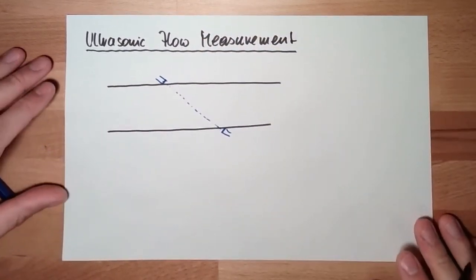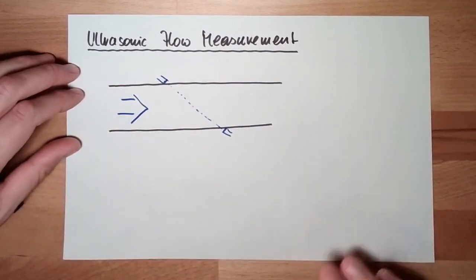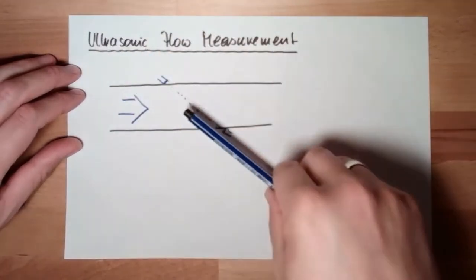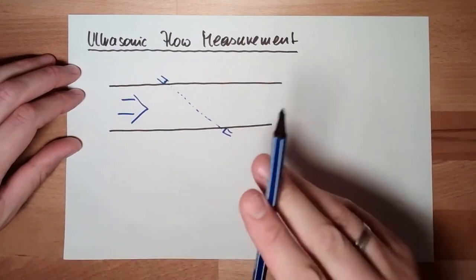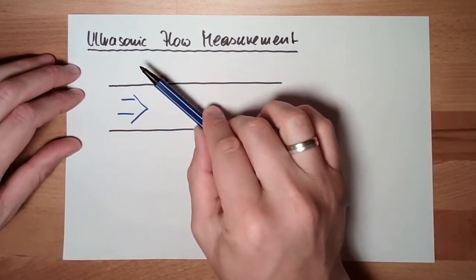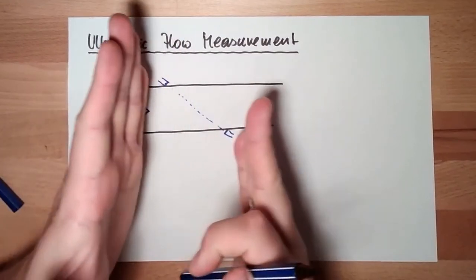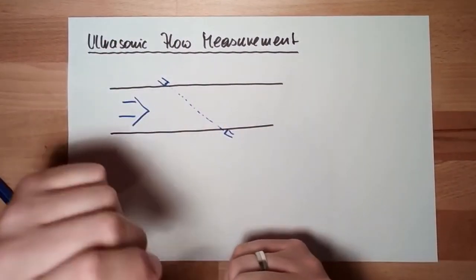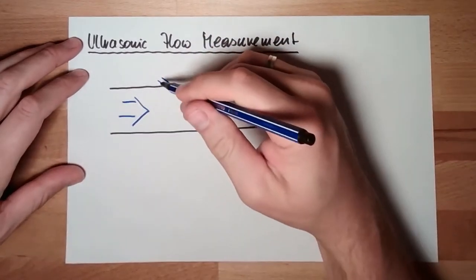It works that way that if we have flow here, the sound in this direction is much faster than this direction, because this here is in stream, this here is against stream. This is why they have to be set apart to measure the difference from this to this and from this to this. Both are sender and receiver.